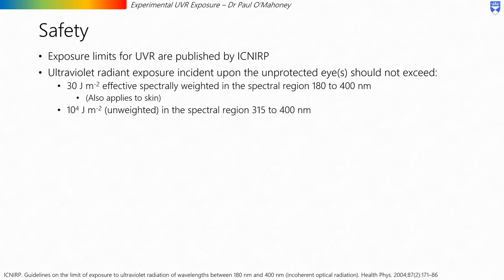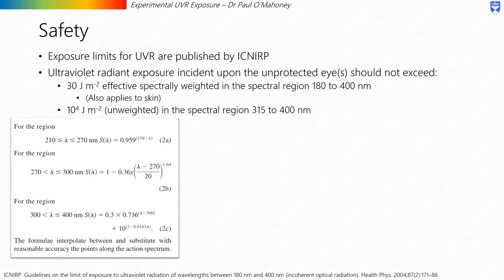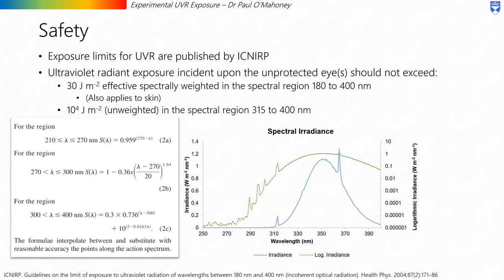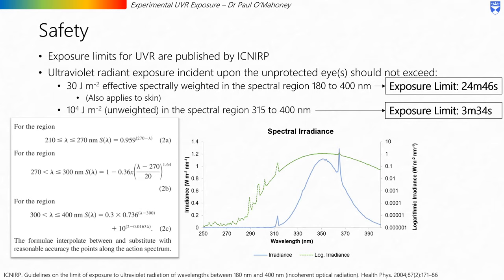The action spectrum referred to when weighting the spectrum can be found using the formulae provided, which can be entered into an Excel sheet to give the relevant action spectrum. As an example, taking our light source from before, we multiply it by the action spectrum, sum together all values to get the irradiance, and then divide that into 30 joules per metre squared — that is radiant exposure divided by irradiance — which gives the maximum permissible exposure limit, in this case 24 minutes and 46 seconds. As both limits apply, we similarly calculate the risk from the second criterion and find a maximum permissible exposure limit of 3 minutes and 34 seconds. We would always abide by the lower of these two values.